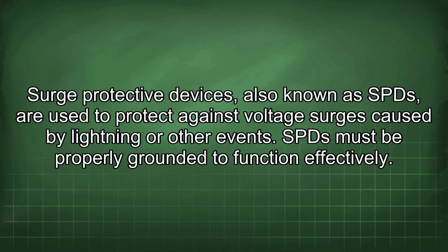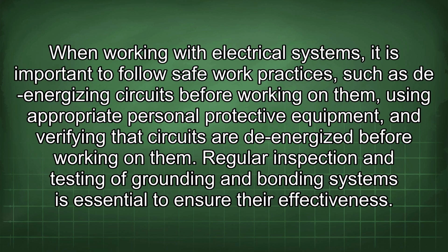Surge protective devices, also known as SPD, are used to protect against voltage surges caused by lightning or other events. SPD must be properly grounded to function effectively. When working with electrical systems, it is important to follow safe work practices, such as de-energizing circuits before working on them, using appropriate personal protective equipment, and verifying that circuits are de-energized before working on them.